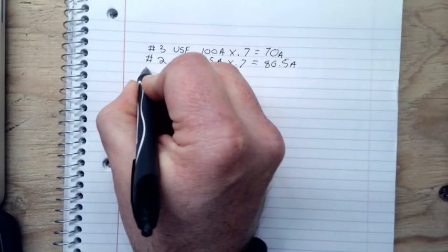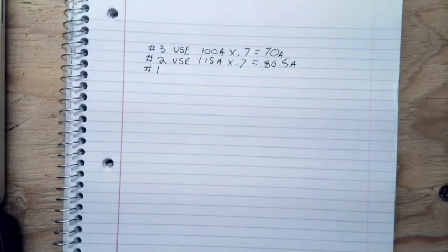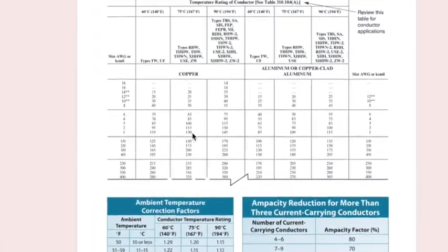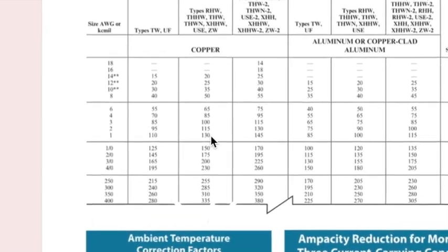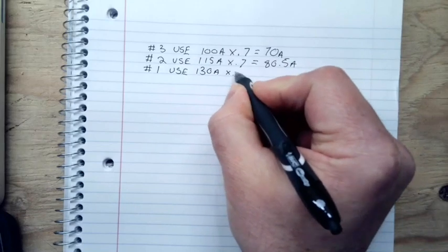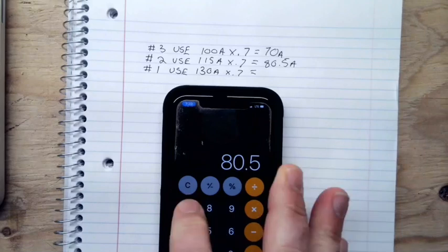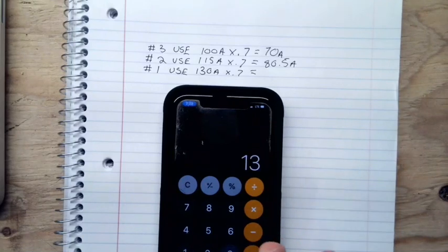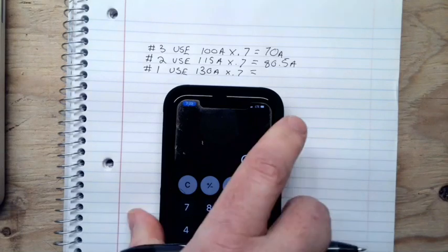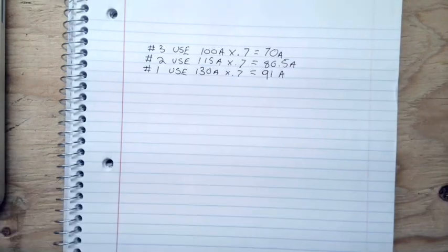So now I'm going to go to a number one. Just because I've been doing this, number one is good to 130. So number one U.S.E. is good to 130 amps times the 70% adjustment factor. So I'm going to take my 130 amps times the 70% equals 91. All right, getting closer to somewhere, but not where we need to be. If I'm remembering correctly, we still need 100 amps.